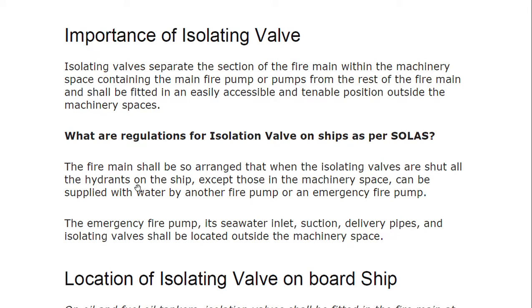The regulation states that the fire main shall be so arranged that when the isolating valves are shut, all the hydrants on the ship except those in the machinery space can be supplied with water by another fire pump or an emergency fire pump. This means all valves on the deck, in accommodation, and in other spaces can still be supplied, while the machinery space is supplied by the emergency fire pump. The sea water inlet, suction, delivery pipes and isolating valve shall also be located outside the machinery space.